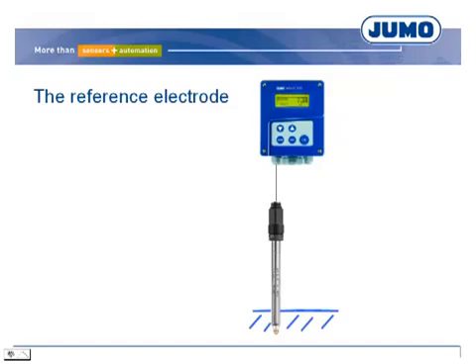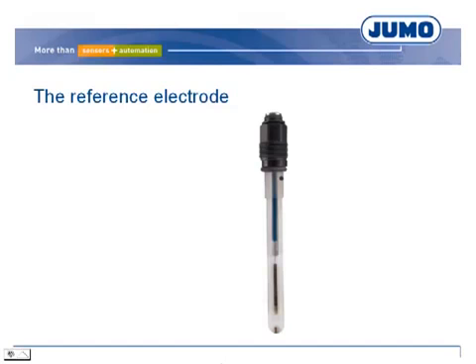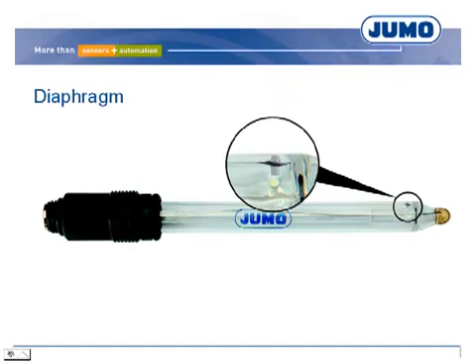The potential on the pH electrode is a measure for the pH value, but the circuit has to be closed. The connection is realized by the reference electrode. The reference electrode transfers the potential of the solution to the head of the electrode via diaphragm, electrolyte, and conductive system. The diaphragm is the connection between solution and electrolyte. The more permeable the diaphragm, the more reliable the measurement — but electrolyte consumption rises and electrode life is reduced.